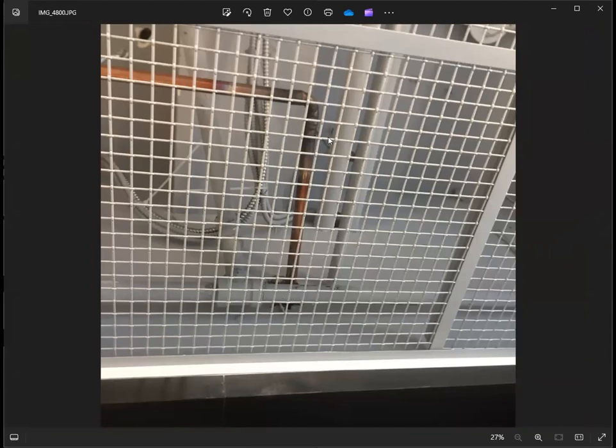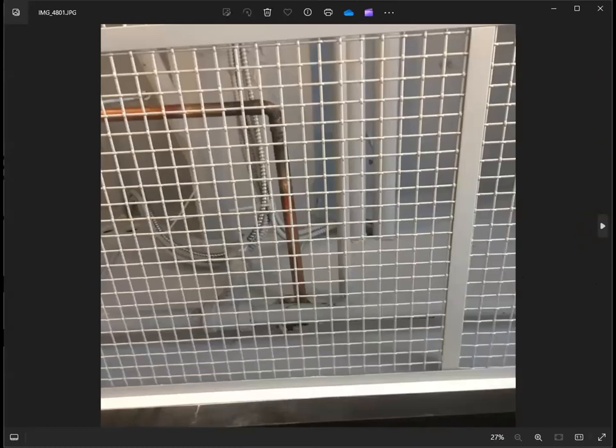This is already concealed. They have a wired ceiling in here, so they need to put insulation on this pipe. The reason is the temperature of the fluid will be reduced, or it might have some condensation on the surface of the pipe, and it will produce some droplets on the floor beneath it, in the area. So they need to complete this, put some insulation on this copper pipe.